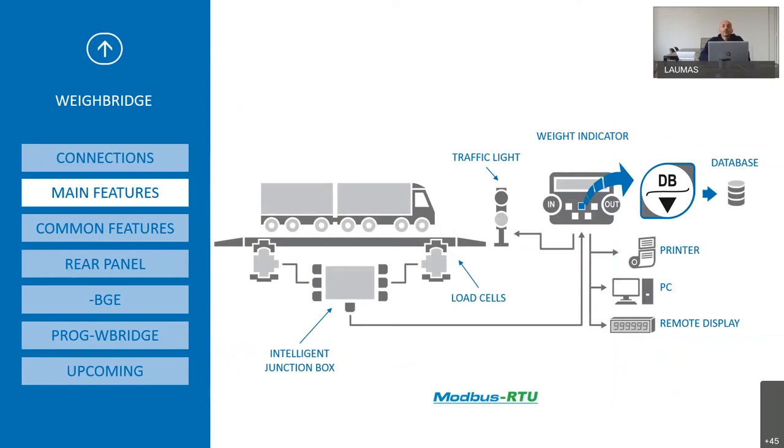Here we can see a complete weighbridge system. The load cells are connected to the intelligent junction box CLM8. The junction box is connected to the Laumas indicator, which manages the traffic lights, records data on its database, allows printing of all data, and can send information to a PC or to a remote display.